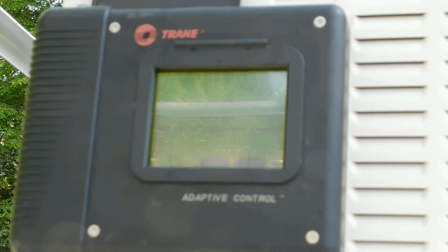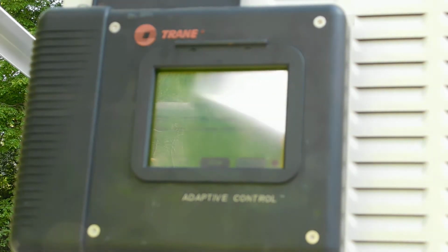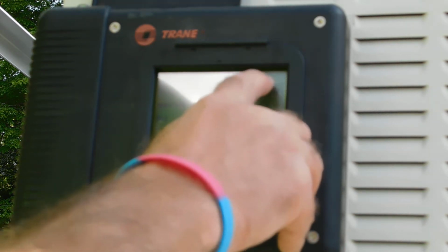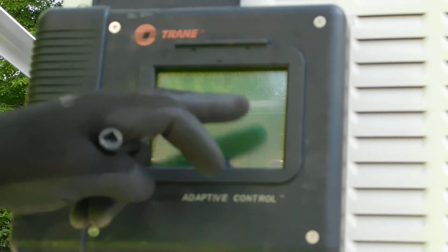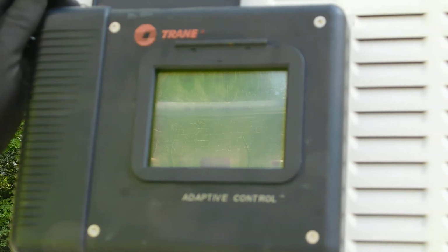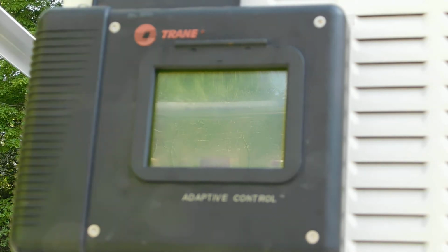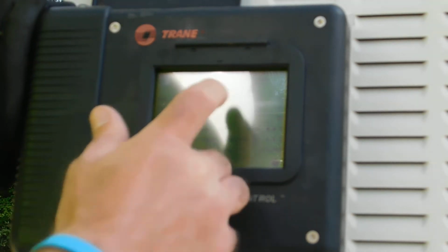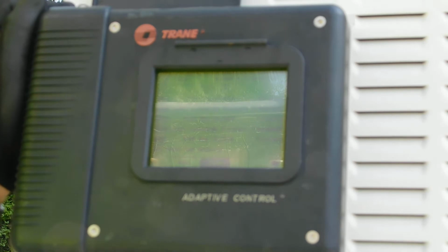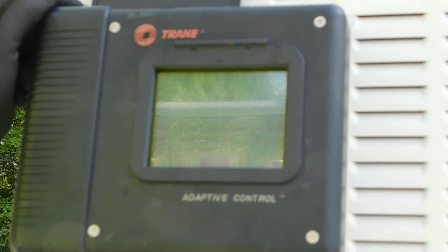Right, so that's back in now. So again, there's the alarm. That's what it says the problem is. Reset alarm. No active diagnostics. Okay, and that's the same with any fault, it will come up in that way. So if it's a suction pressure, a water problem, a fan, it will come up and tell you there's a fault. Also in the main reports, down the bottom you've got historic diagnostics, and that'll tell you all the diagnostics you've had up to a certain amount.